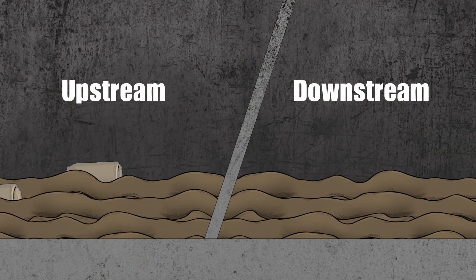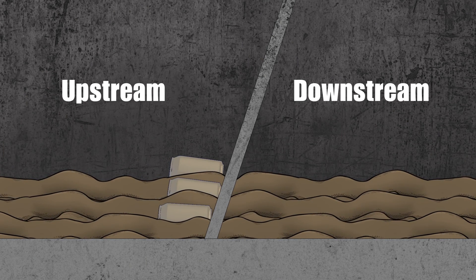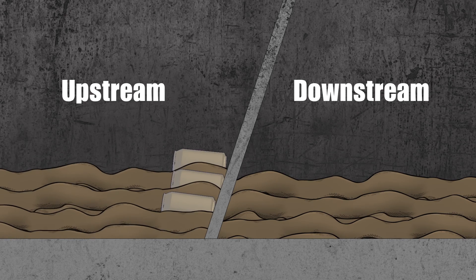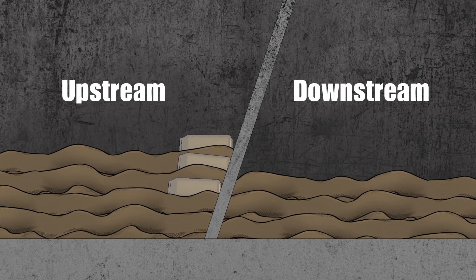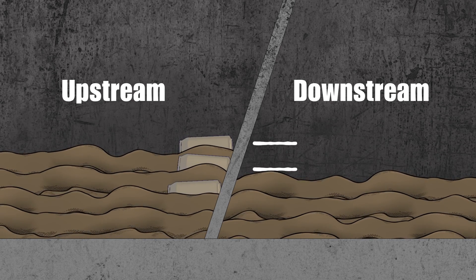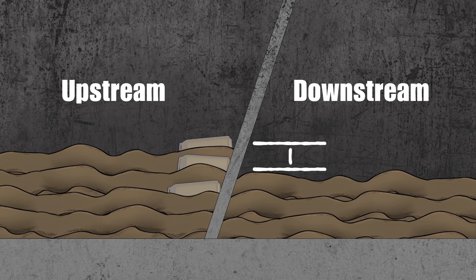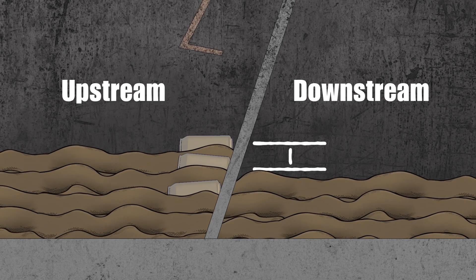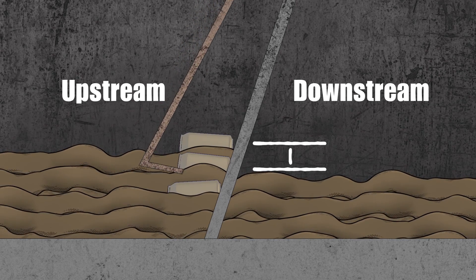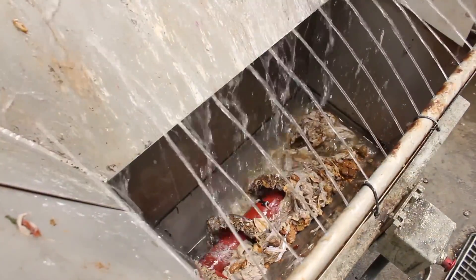Under normal operation, the bar screens run automatically based on pressure differential. When debris accumulates on a mechanical bar screen, the water level upstream rises due to the obstruction. The level sensors evaluate the increased upstream level relative to the downstream level. When the difference in the two water levels reaches the set point, the mechanical bar screen automatically starts. The screenings are discharged directly from the mechanical bar screens into the compactor feed hopper.